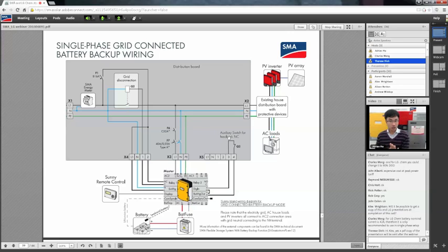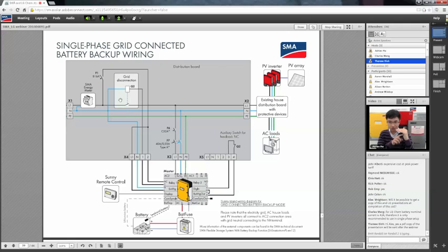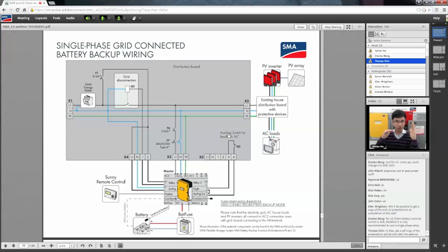When the system is energized, Q2 will close - obviously, you're connecting to the grid. Q2 will be closed, which results in the auxiliary switch being in the open position. You can see in the circuit, on the X5 circuit, it actually connects to the battery voltage. So when you're connecting to the grid, the auxiliary switch is open, so you get no voltage. The Sunny Island senses the system is fine - grid connected, 0 volts for the feedback signal. The system works fine.